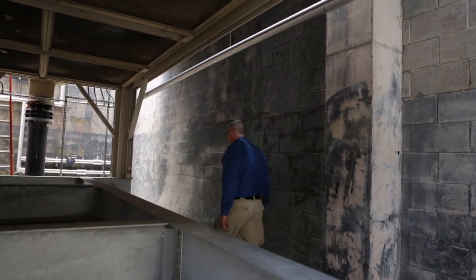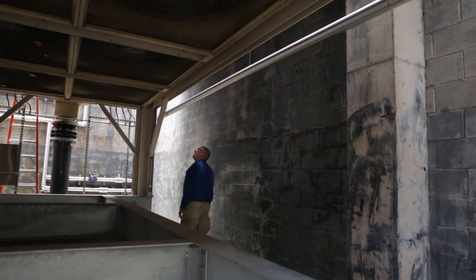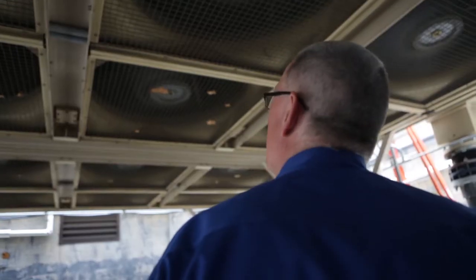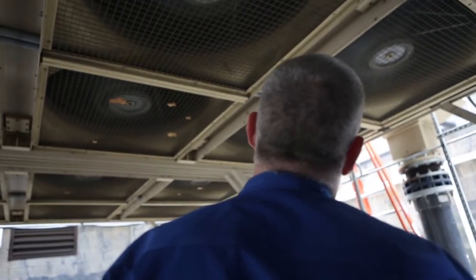On a conventional cooling tower, it has 1 or 2 fans. If you lose one of those fans, one of those fan motors, you lose cooling capacity. With the Tower Tech tower, each one of the cooling towers that we have, based on the size and the capacity, has 8 fans. They're 7.5 horsepower fans. They're easy for my maintenance crew to change out. They can do it without hiring outside contractors. The fans and the motors are readily available. They're in stock. And if we lose a fan or a motor, we only lose 1/16 of our total cooling capacity. Whereas with our original configuration, and even some of the newer competitive brands, they might have 4 fans in their array. So if you lose 1 fan, you lose 25% of your capacity.